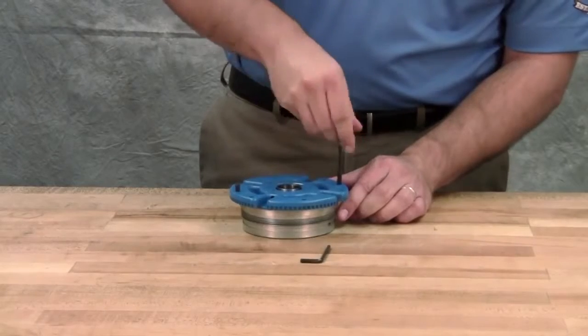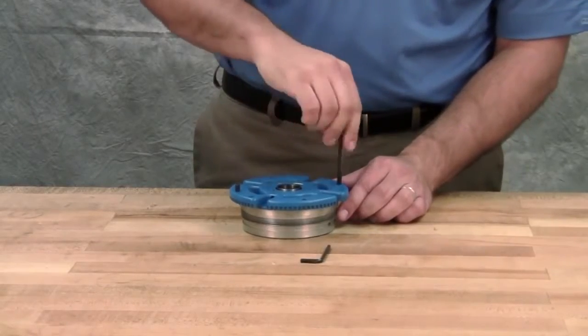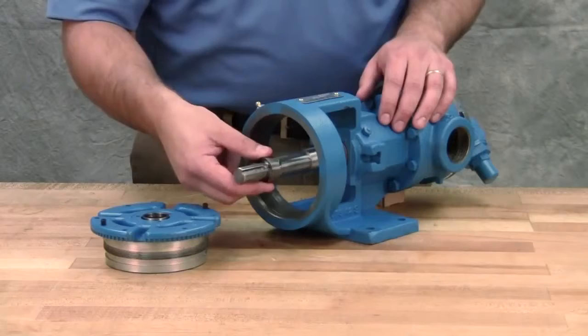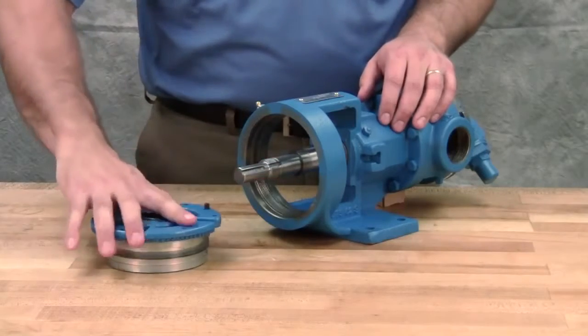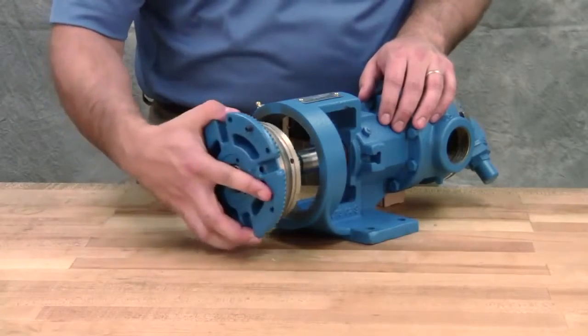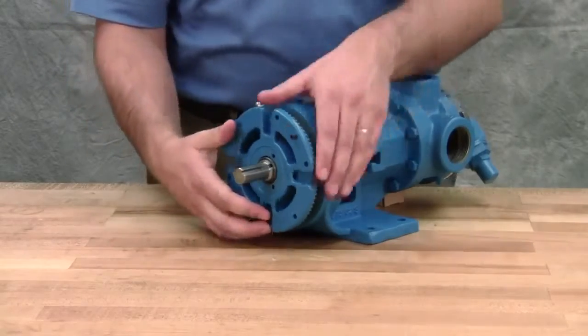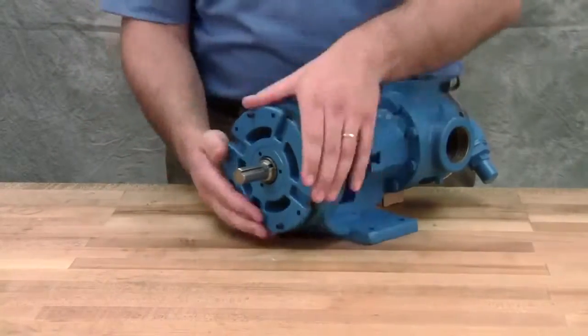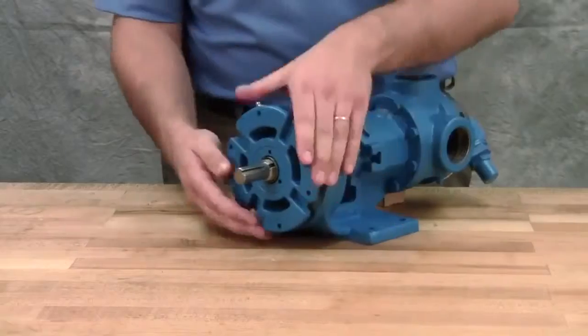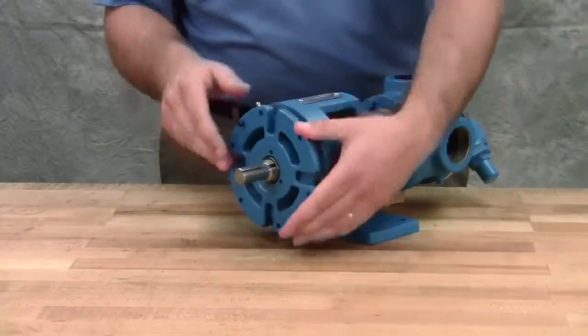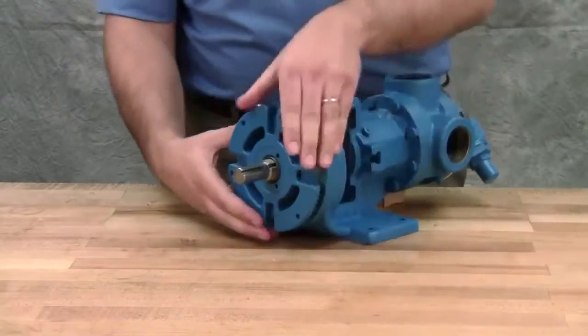H and HL sized pump bearing spacer collars are not recessed and do not have the half-round rings. Slide the inner spacer collar over the shaft with the recessed end facing the rotor. Place a pair of half-round rings on the shaft and slide the inner bearing spacer collar over the half-round rings to lock them into place. Turn the bearing housing into the bracket.